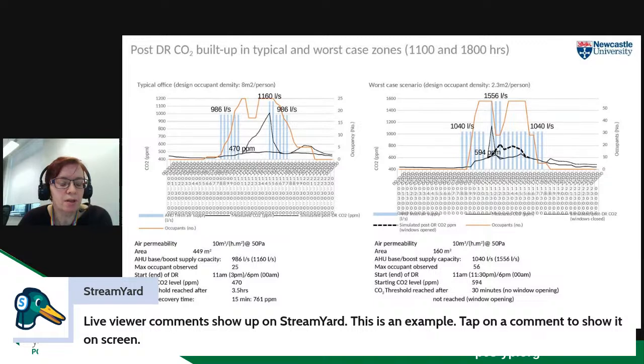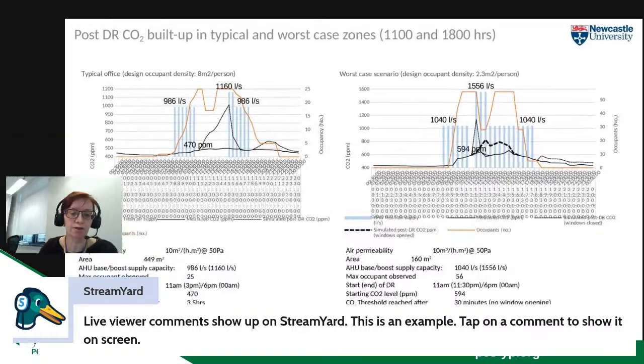The worst case scenario room doesn't have openable windows, but if it did, then the heavy black dashed line shows what the CO2 would look like. So in that worst case space, we would be able to offer more demand response if the window was open, because we wouldn't get to 1,000 parts per million. But what this essentially shows us is we can offer demand response using the air handling units, and for most of the typical office spaces, we can offer 3.5 hours of demand response before the carbon dioxide levels get too high, and that is with the windows shut. So you can offer longer if the windows are open and providing that fresh air, instead of the air handling unit offering the fresh air.